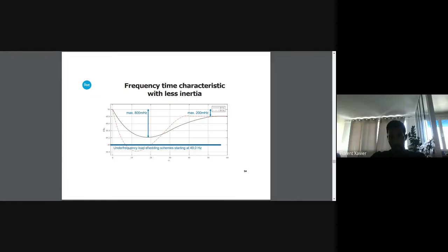Typically, in our system, the rules specify that the frequency cannot go below 49.2 hertz. This is the black curve with inertia of 5 seconds. With massive integration of renewable energy and power electronic devices, we will have less inertia on our system. And if you reduce the inertia, the rate of change of frequency and the first deviation will be more important. And that's what we can observe in this curve.